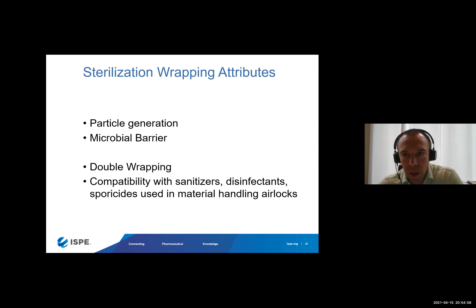So what we did at STERIS is took a look at the differences of the materials in a few different simulation studies. These are in-use simulations. This one here, we simply peeled open different pouches of different materials. We peeled these pouches open in a controlled ISO 5 class hood. All the time we were monitoring the air quality, so we were collecting particle counts in the ISO 5 hood and enumerating particles of 0.5 and 5 microns in size.